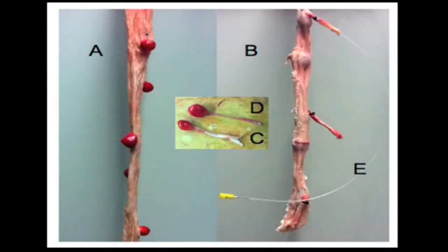Inside the suitcase, porcine bowel is used to simulate human colon. These specimens are cleaned and completely everted to expose the mucosa, as demonstrated by picture A. A polyp mix, which solidifies at room temperature, is injected into the mucosa to produce a sessile polyp. Pedunculated polyps are created using the same mix and attached to the bowel in a standardised fashion. The bowel is then inverted to restore the normal anatomical position, as demonstrated by picture B.